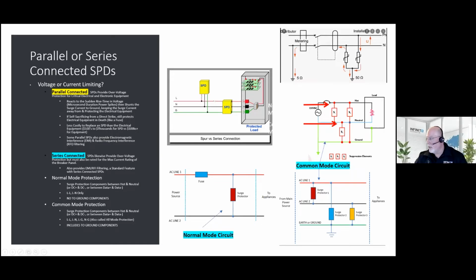So you would use a common mode in areas where the power quality is just terrible. But otherwise, if you're familiar with the Motorola R56 standard for land mobile radio, they say thou shalt never use a common mode protector. And the reason is that, for that moment of shunting of surge current, the ground connection could possibly create a ground loop scenario. For critical 911 radio systems, they don't want that to ever be a possibility. So they say, thou shalt not use common mode. But if you're at the end of the power line in a rural area and your power is crappy, you kind of might want a common mode protector. So there's reasons, and you just got to weigh things and decide which one you need.